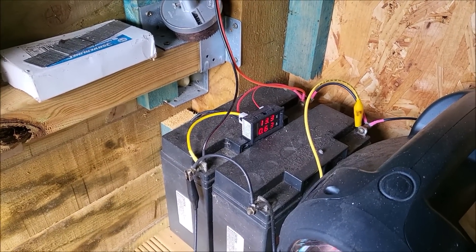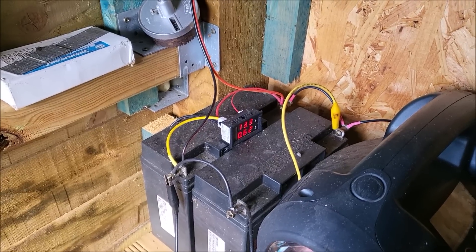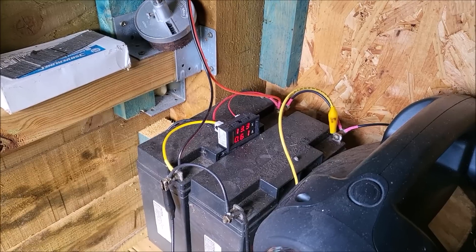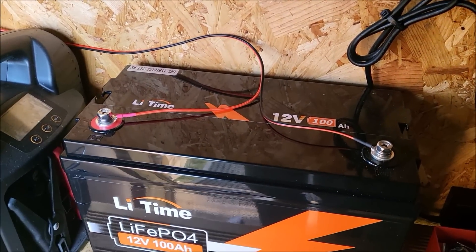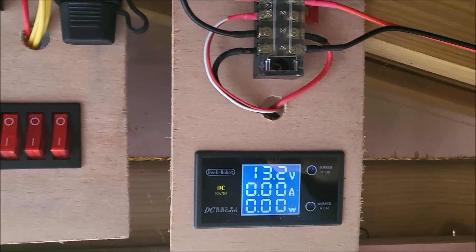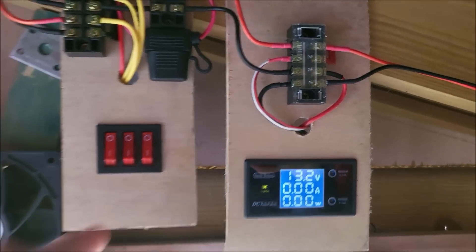This system will now just get charged up to whatever the charge controllers charge it up to — 14.2 in the morning and about 13.5 in the afternoon. That's the wire attached to the lithium iron phosphate battery. That now goes up to the lighting board. 13.2 volts is the voltage across that battery.